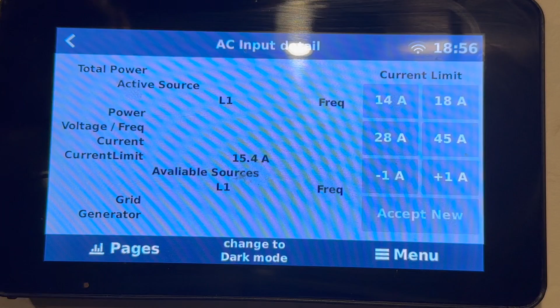Now to get around this, what we recommend you do is adjust your input current limits just a little bit down. So you can see I have a couple of presets here: 14, 18, 28, 45. And you can see those are all just a little bit lower than what I might typically connect to. My 14 amp is for the smallest 15 amp shore power cord that I may ever connect to.